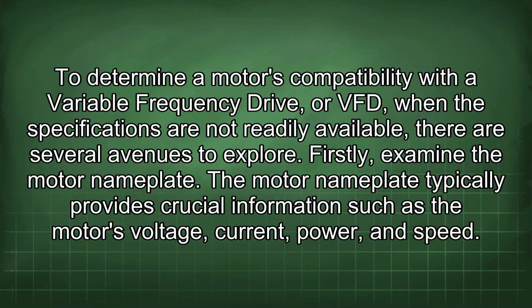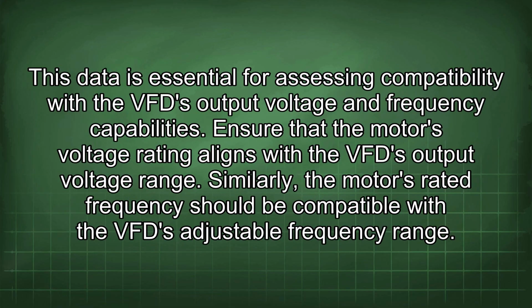To determine a motor's compatibility with a variable frequency drive, or VFD, when the specifications are not readily available, there are several avenues to explore. Firstly, examine the motor nameplate. The motor nameplate typically provides crucial information such as the motor's voltage, current, power, and speed. This data is essential for assessing compatibility with the VFD output voltage and frequency capabilities.